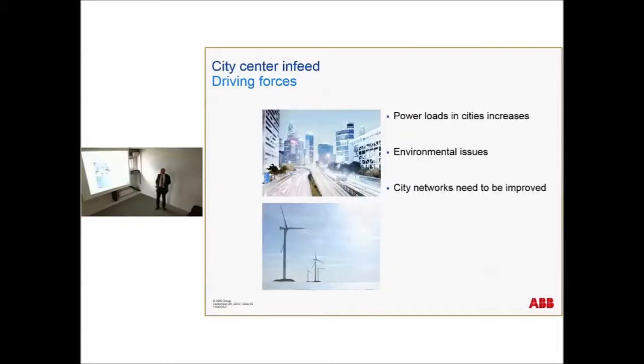Also, city center infeed is the same here. Normally in Asia, you have these rapidly growing mega cities that require more and more power, but they have problems getting the power into the city center. And normally the only solution is to have new cables added. And you can't add AC cables for more than a limited distance. So the only solution is they have to use the HVDC Light technology.